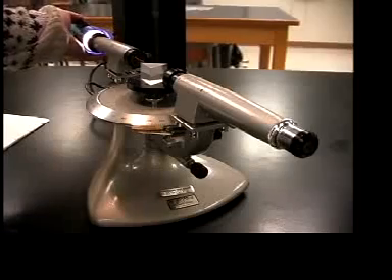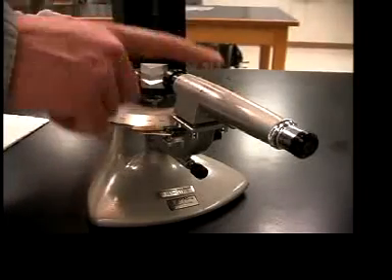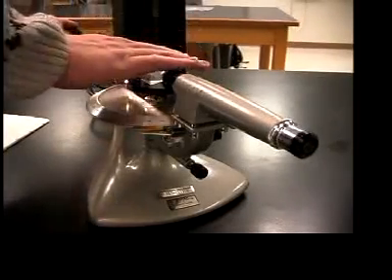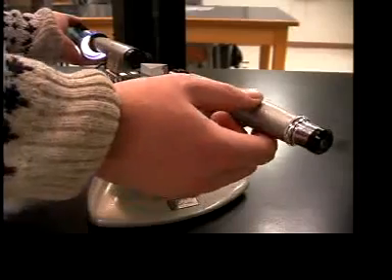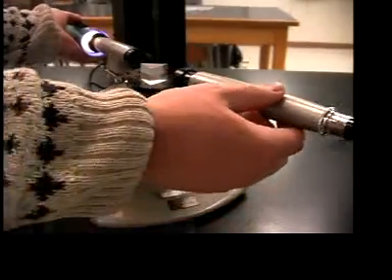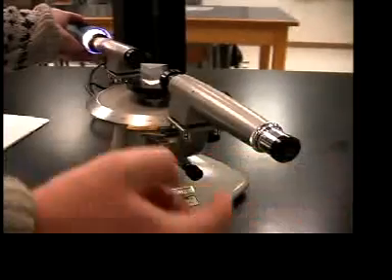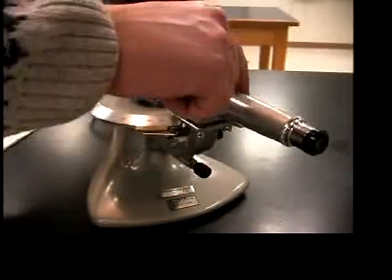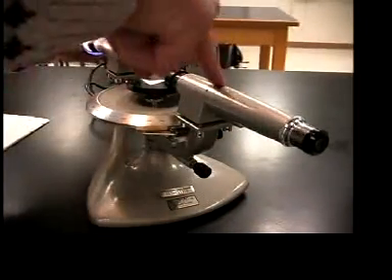The first setup step you need to do is align these two in a parallel manner, disregard the prism for now. Make sure the telescope is loosened down here with this knob, and just move this around while looking through here until you have it lined up, so in other words, 180 degrees around.